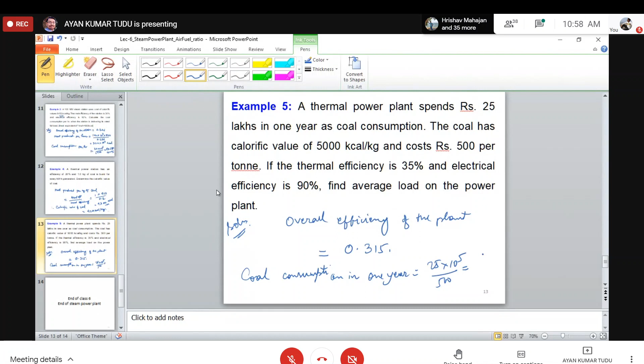Then what we have to find out? So we have to find out the coal consumption in 1 year. From that we'll be finding out the heat produced in 1 year, and from that we'll be finding out the heat output in 1 year. So coal consumption in 1 year. How much is the coal consumption? It says 25 lakhs in 1 year as coal consumption, and the cost is 500 per ton, right? Then 25 into 10 to the power 5 by 500 gives how many tons? 5000 tons, right? 5000. Okay, it is easier to convert tons into kg, correct? So we're converting it to kgs. So it is 5 into 10 to the power 6 kg, correct?